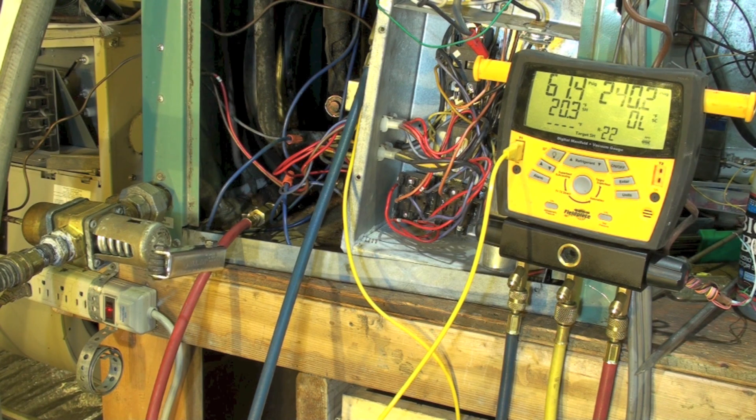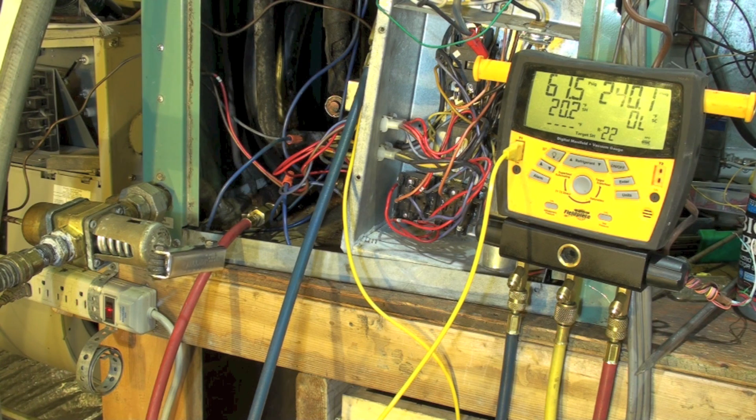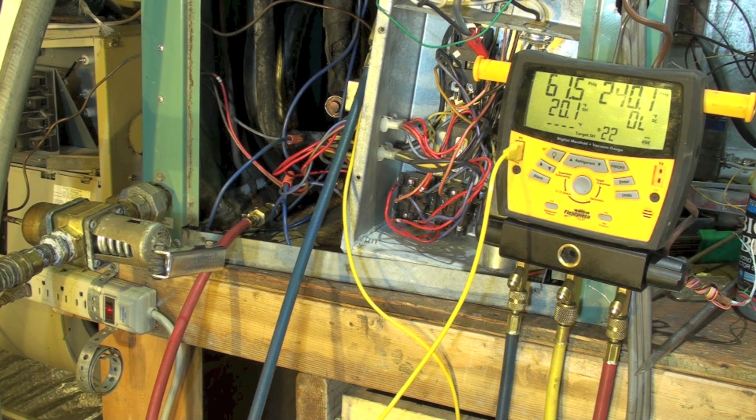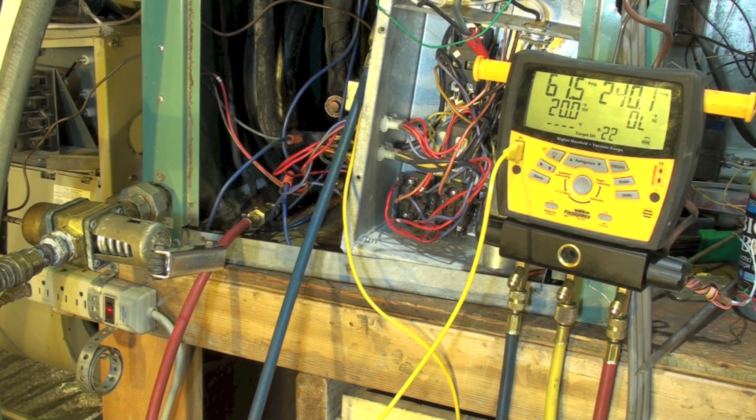Okay, we're pretty well settled down. The discharge water temperature is about 103 right now. Head pressure is down to 240, my suction pressure has gone down quite a bit - 61 and a half. We've got 20 degrees of superheat now. Let's drop the head a little bit more.